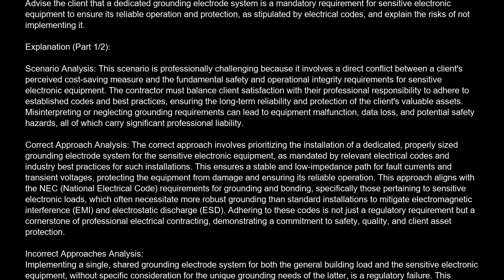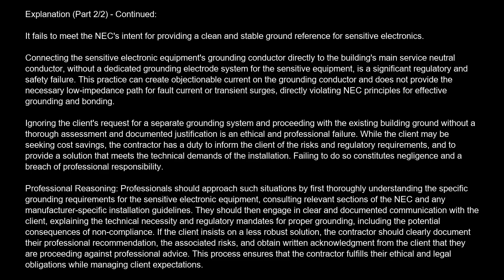Incorrect approach analysis. Implementing a single, shared grounding electrode system for both the general building load and the sensitive electronic equipment, without specific consideration for the unique grounding needs of the latter, is a regulatory failure. This approach risks introducing noise and voltage fluctuations from the general building system into the sensitive equipment, compromising its performance and potentially causing damage. It fails to meet the NEC's intent for providing a clean and stable ground reference for sensitive electronics. Connecting the sensitive electronic equipment's grounding conductor directly to the building's main service neutral conductor, without a dedicated grounding electrode system for the sensitive equipment, is a significant regulatory and safety failure.